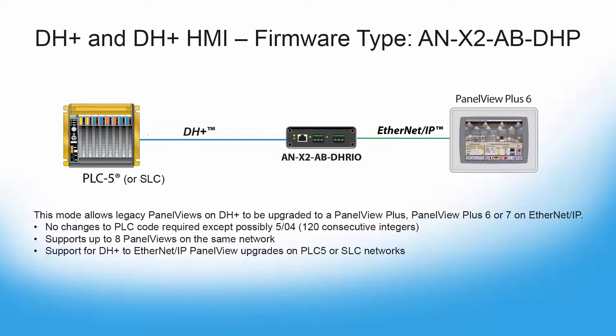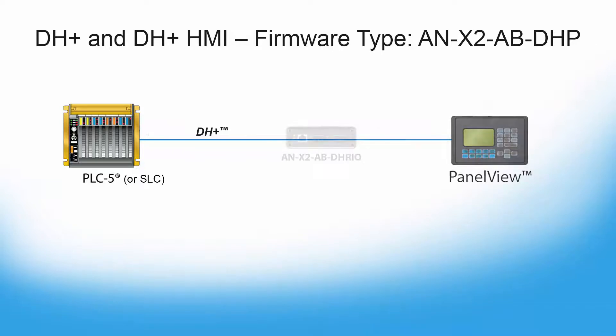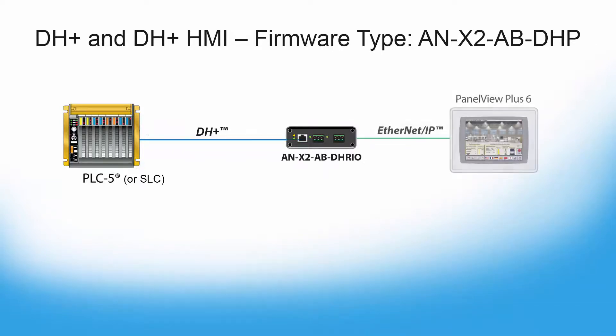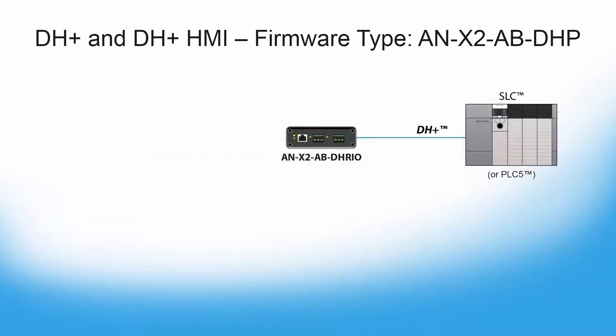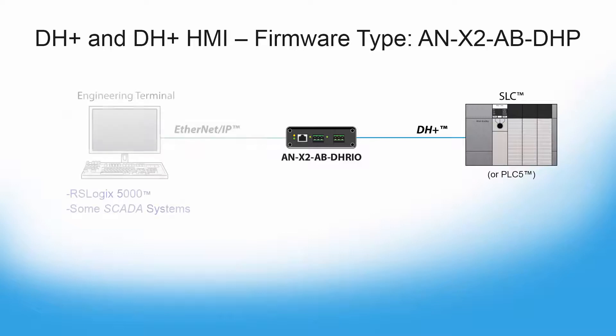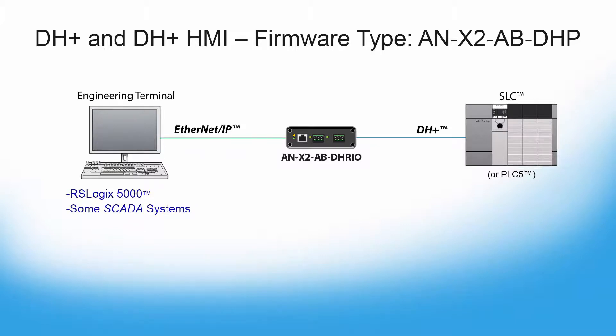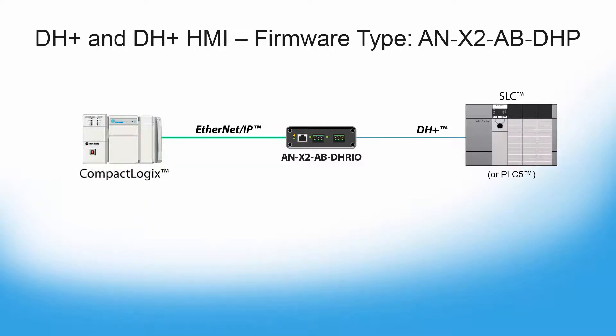The ANX2ABDHP firmware is used for all Ethernet IP to Data Highway Plus applications. Typically you would use it to integrate new Ethernet IP panel views with DHP PLC5s or SLCs. You can also monitor and program a PLC5 or SLC on DHP via RSLogix 5000, or use some SCADA systems to control or monitor Data Highway Plus controllers. It's also possible to message between a Rockwell processor on Ethernet IP and an SLC on Data Highway Plus. Any application that involves interfacing with devices on DHP would require this firmware.